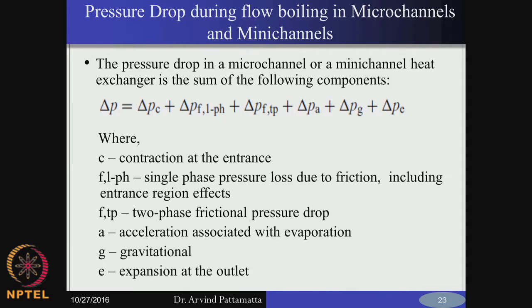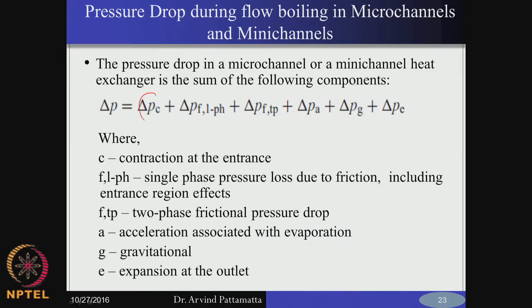Pressure drop estimation becomes very important. The added complexity is that you have two phases. For a microchannel or mini channel, you have different contributions to the overall pressure drop — similar to single phase liquid flow, you have contraction losses and expansion losses. There could be some influence of gravitational head, but this can be neglected most of the time.